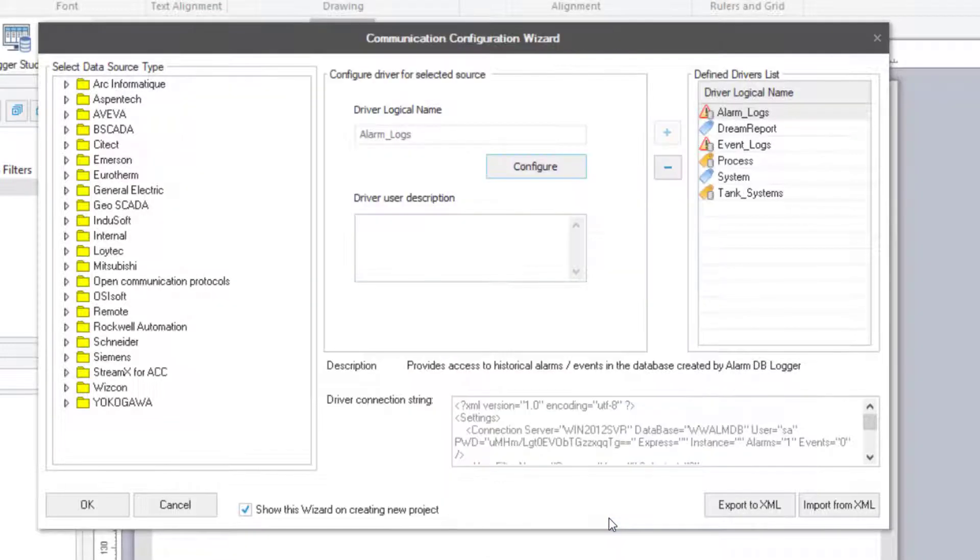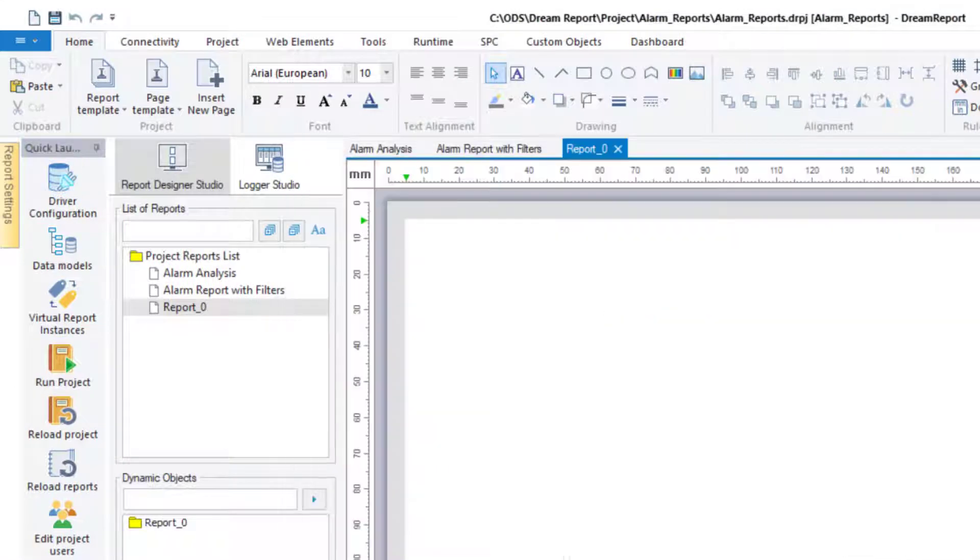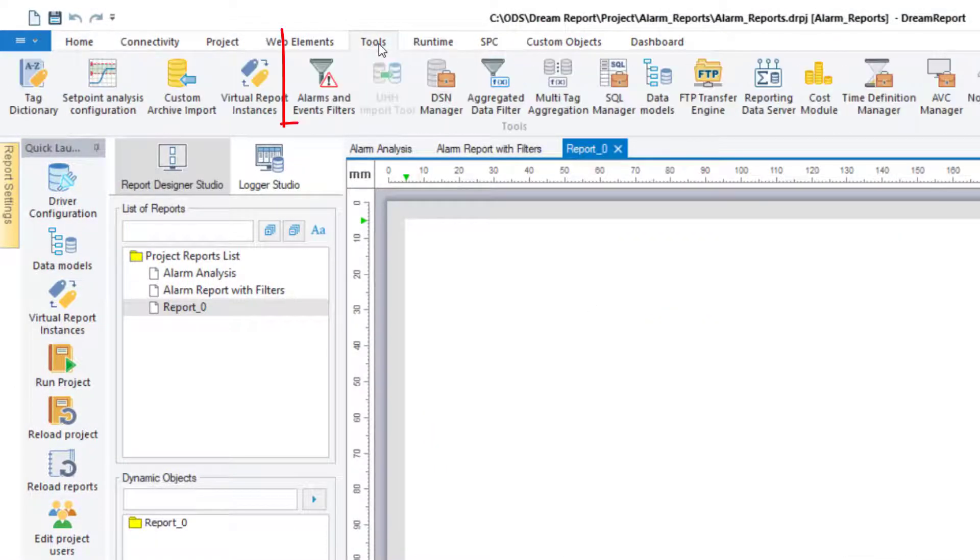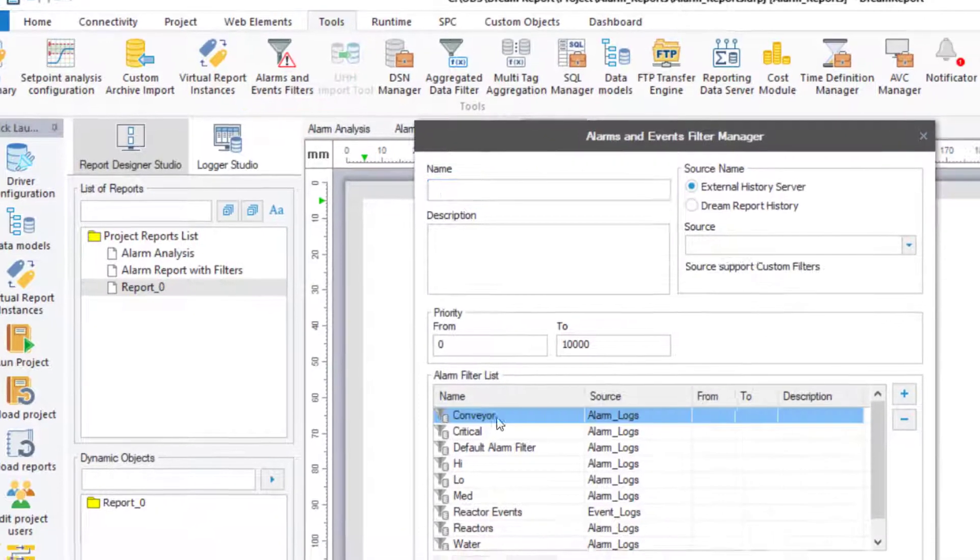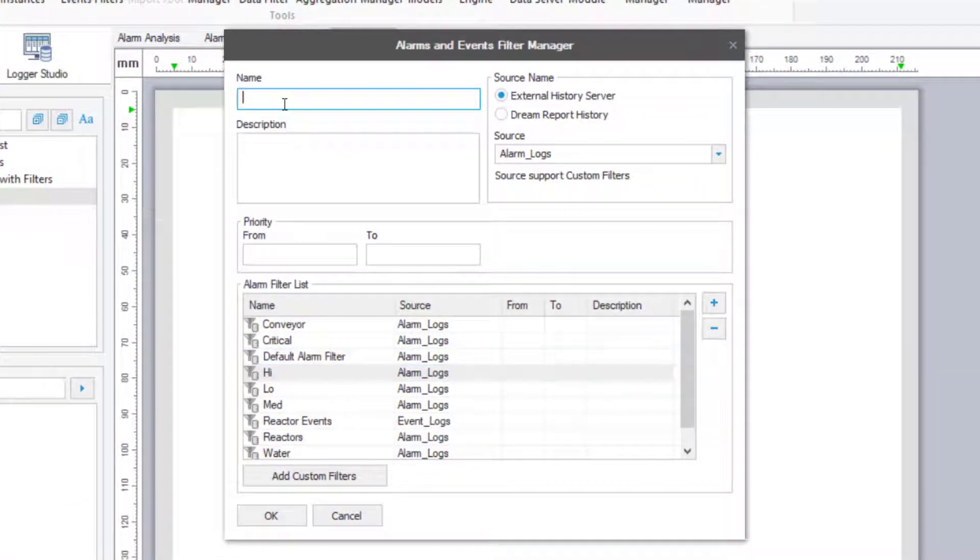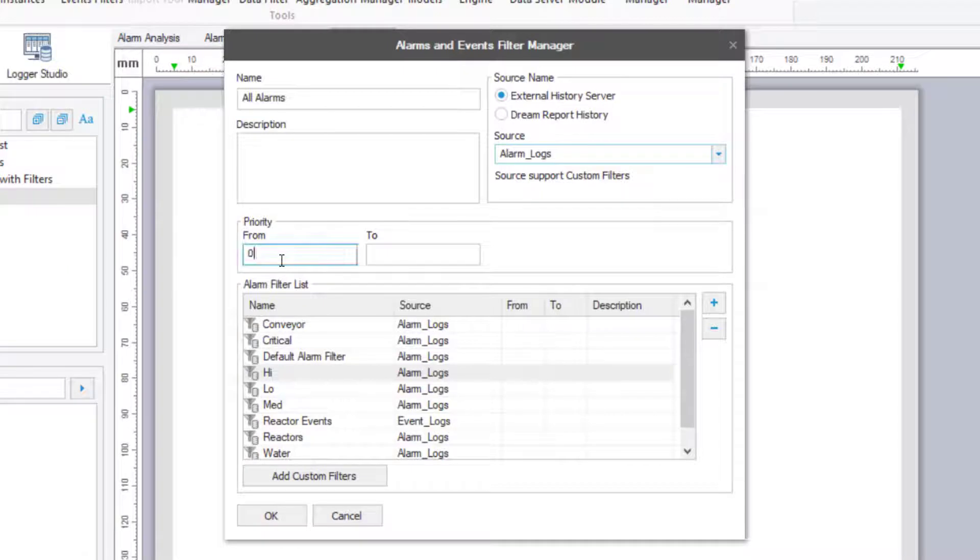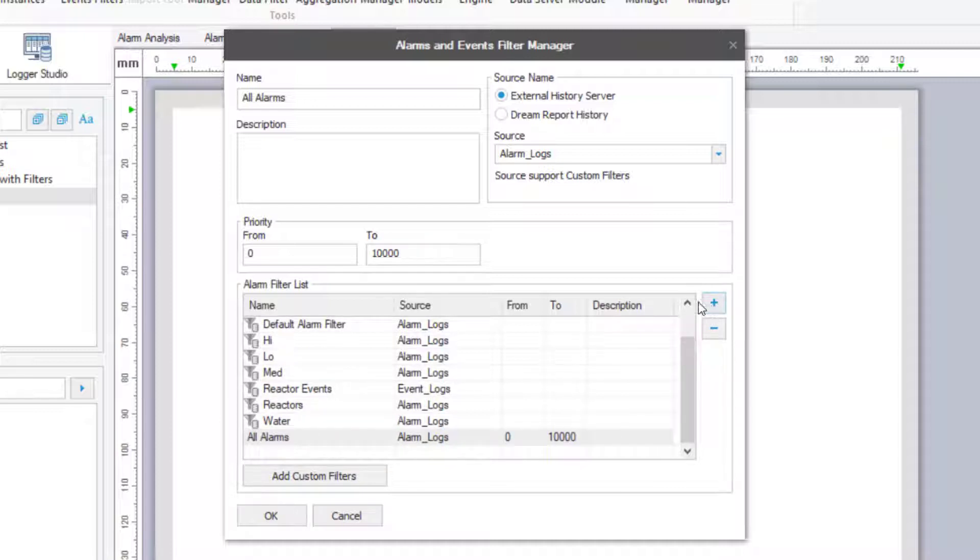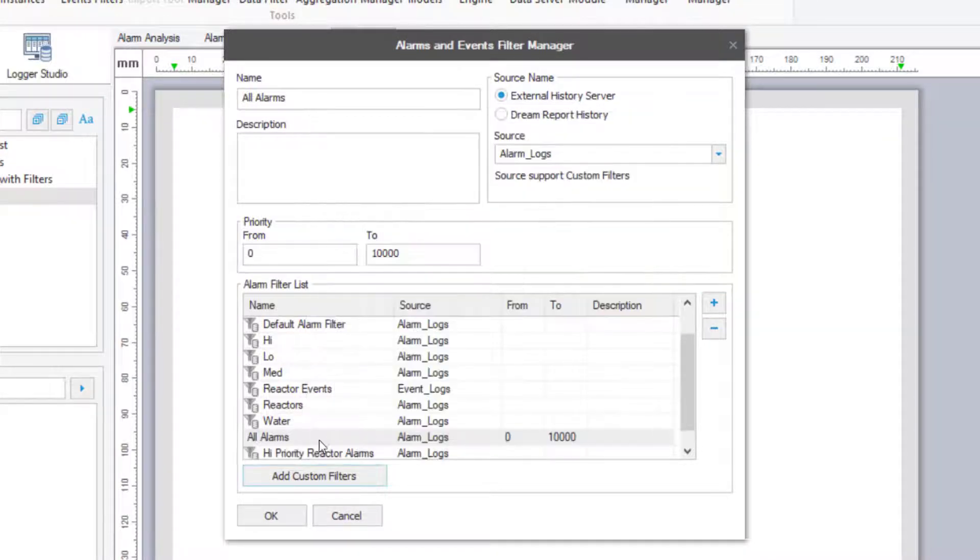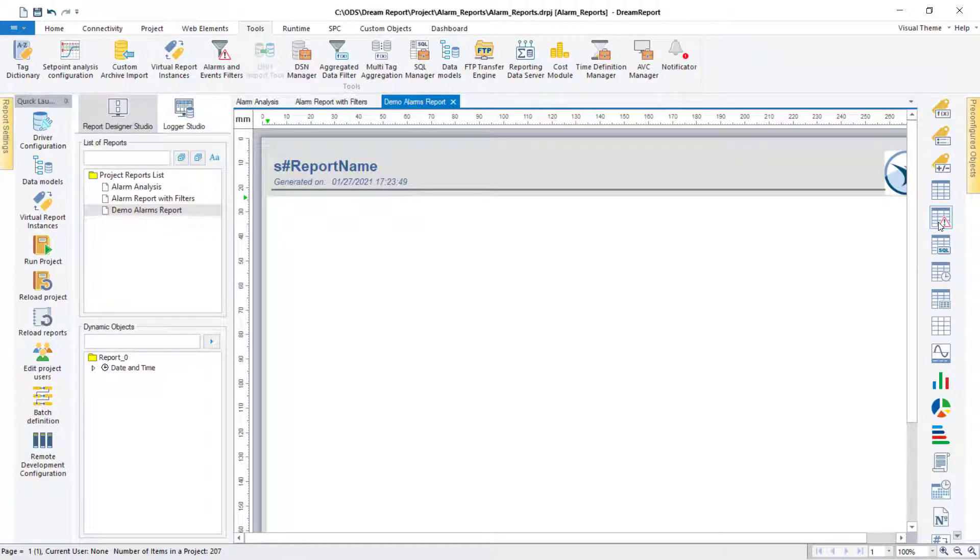Now that the alarm driver is configured, I need to let the rest of the project know all about the alarm filters. Using the Alarm and Events Filters tool, I can either specify priority-based alarm filters, or add the custom filters I had defined in each alarm driver. Here, I'll select the alarm source I've created ahead of time, and select and add its custom filters. At this point, these filters can be accessed from the reporting objects.